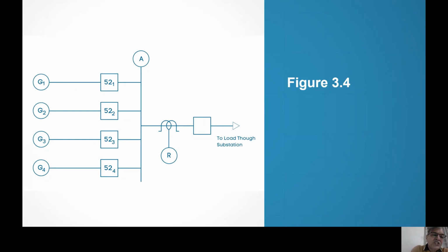I've got four generators, G1, G2, G3, and G4, controlled by breakers 52-1, 52-2, 52-3, 52-4. And then there can be many lines. Say one of the lines is going to load, going to some substation on which I've got relay R. Now at daytime, all four generators are running, but at night time, the load is less.